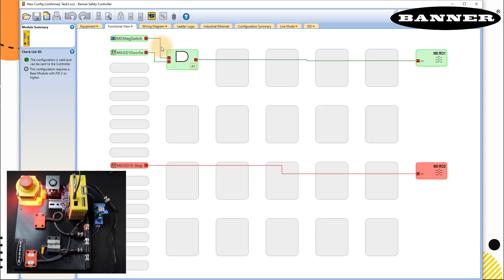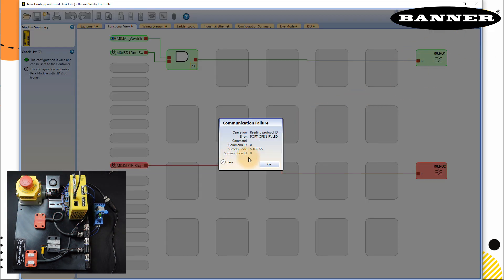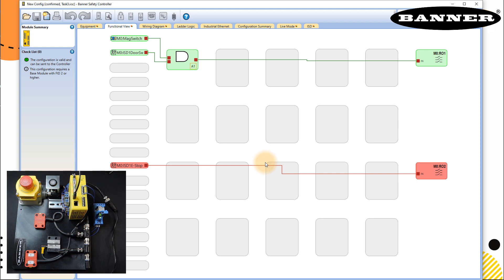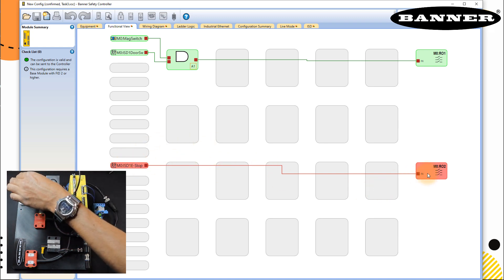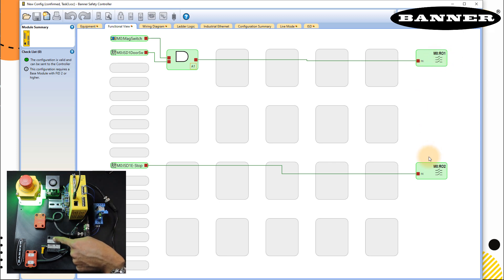Now I can go to the live mode. You can see that the status of these two door switches are true, so my RO1 is true. Some communication failure, but it's okay. E stop is false, so RO2 is false. Let's reset my E stop. Now in this case, my RO2 is also true. So my circuit is safe. Both of my outputs are true.